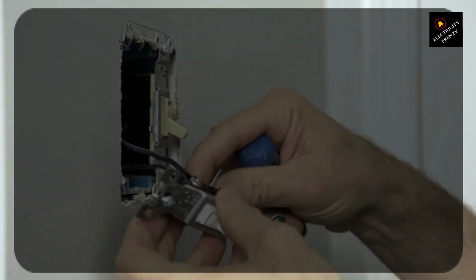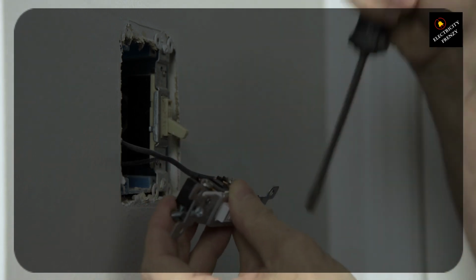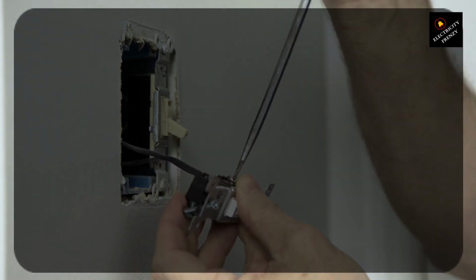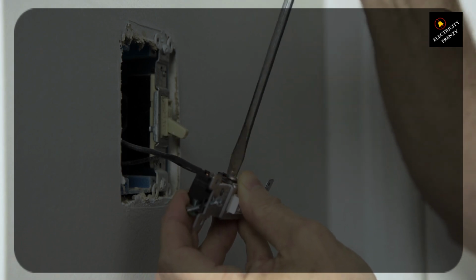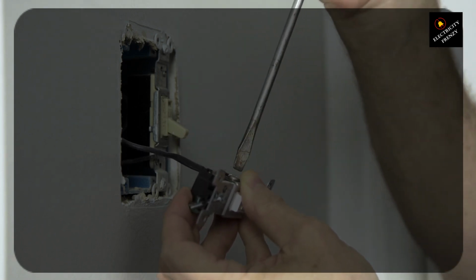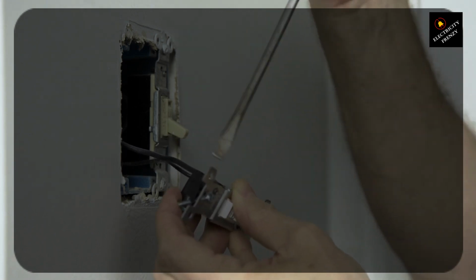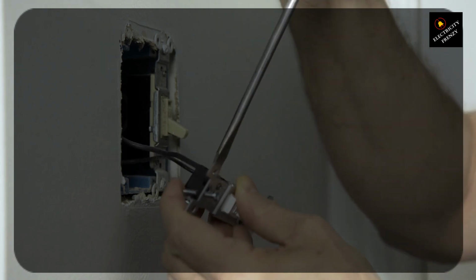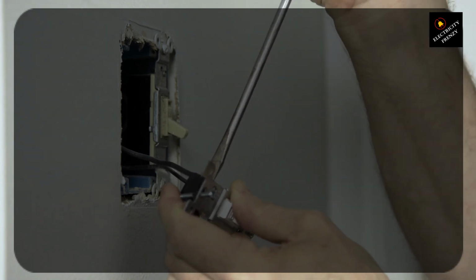Navigating the troubleshooting maze. Detective work required. Pinpointing the problem requires observation. A breaker that trips often under normal load suggests an overload issue. Immediate tripping post-reset hints at a short circuit. Addressing overloads and short circuits.